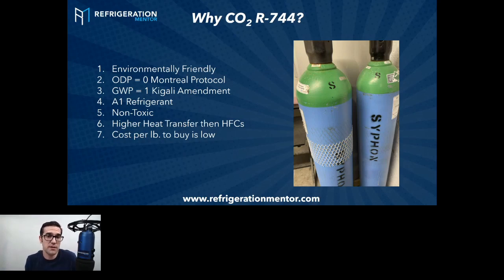One of the cool things about CO2 that I've been learning over the last 6, 7, 8 years is that it has a really high transfer of heat. So it has a very high coefficient of performance, a lot of BTUs per pound, which gives it a lot of advantages when designing systems. If you're working on or designing systems, you'll see the pipes are a lot smaller than what you normally work on, because you can move more heat.